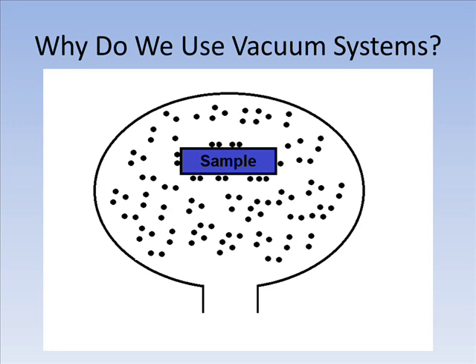High vacuum and UHV are vacuum regimes obtained in advanced vacuum systems, but why do researchers go through the trouble of creating these extremely low-pressure environments? There are a number of applications that require the use of high and ultra-high vacuum systems, because of the incredibly low amount of interaction between experimental samples and low-pressure gases. At atmospheric pressure, gases interact with experimental samples, coating them with layers of contamination and changing the surface chemistry.